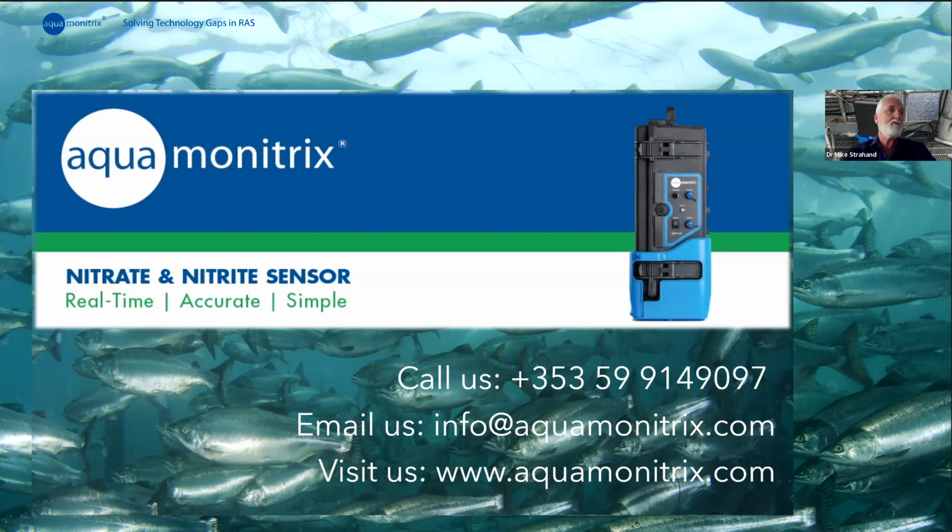So if there was a situation in an aquaculture where you were increasing the salinity, maybe as we're going from small fish up to smolts, you might see an increase in salinity as you're going through that process. You wouldn't have to recalibrate the monitor. So hopefully that answers that.